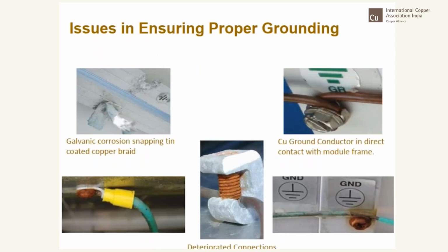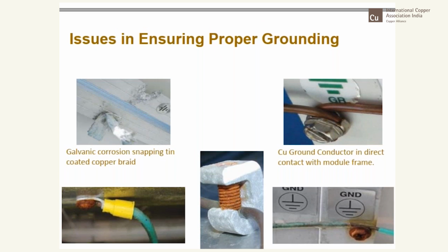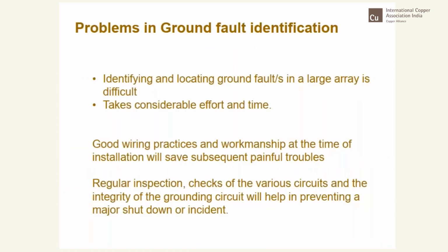So issues in ensuring proper grounding: you can see these are all the failures which have happened. Galvanic corrosion has taken place. When you have two dissimilar metals in contact, obviously corrosion takes place. And here you can see copper in contact with the aluminum frame, so that has caused this. The braid has become weak, and then it has ultimately snapped. And then you also see the terminals getting corroded, and you see the copper ground conductor in direct contact with the mounting frame.